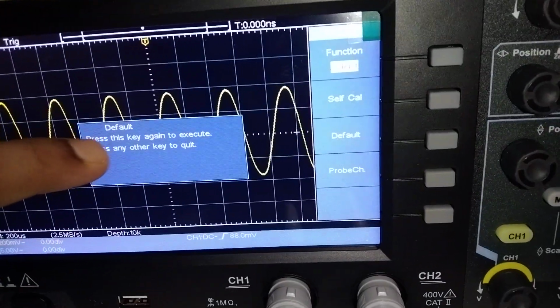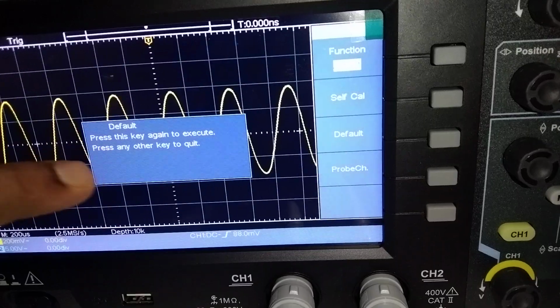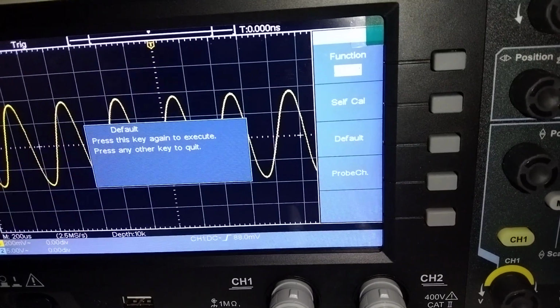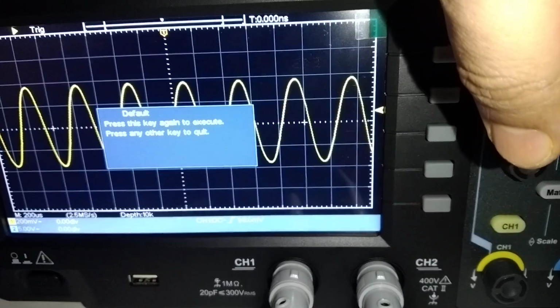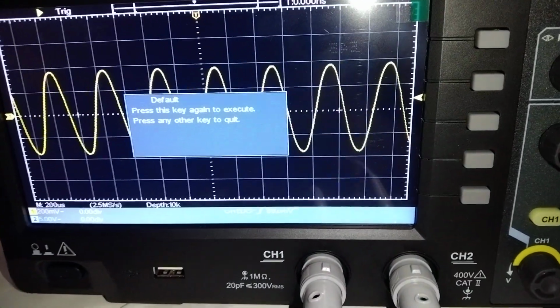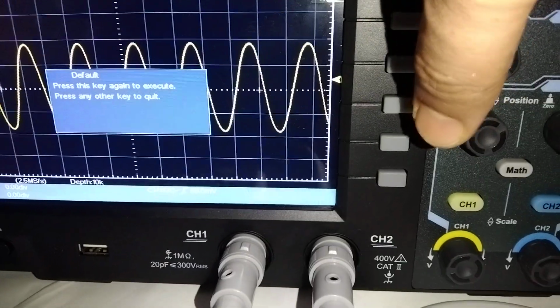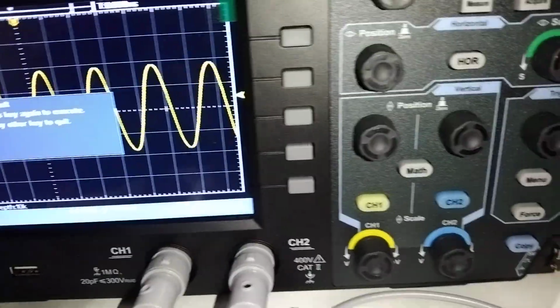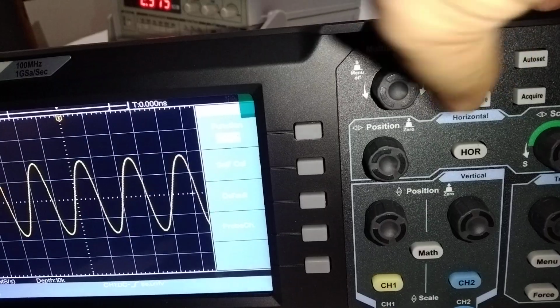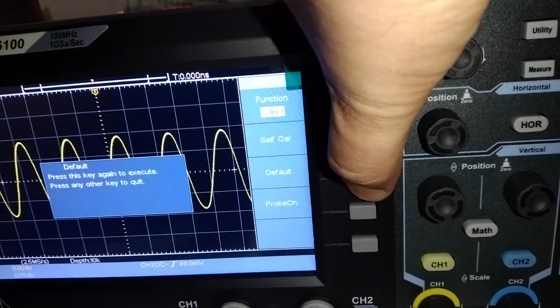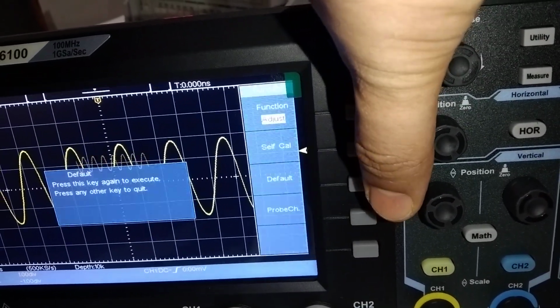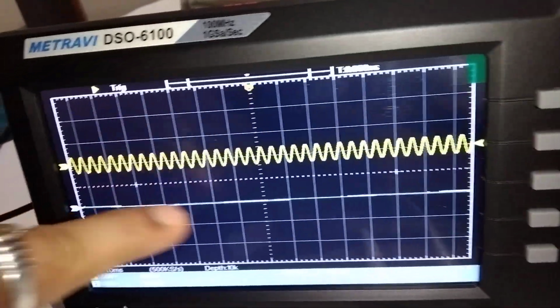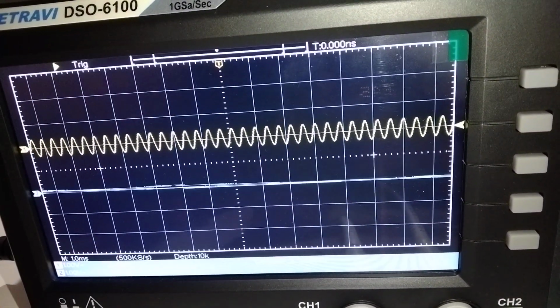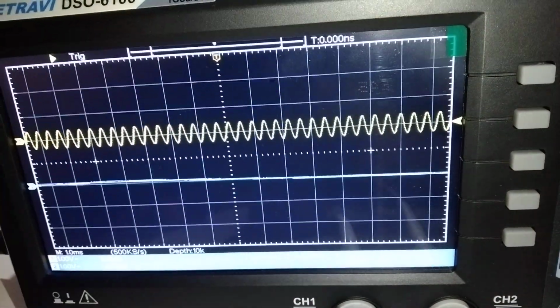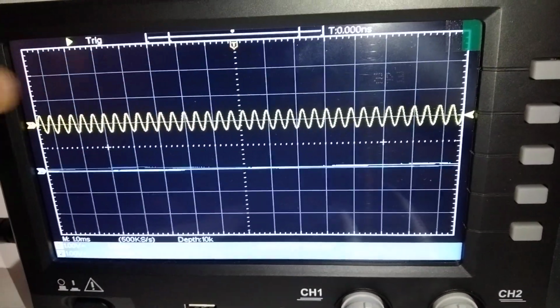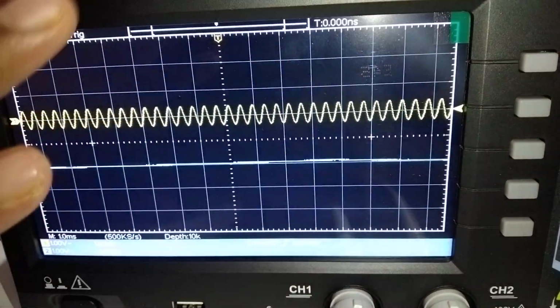Default: press this key again to execute, press any other key to quit. So the default attenuation coefficient set value of the probe. So you have to again press the default. So utility, default, then we'll execute. So here you can see that channel 2 has appeared. Initially there was no channel 2. I hope you understood. Initially only channel 1 was there. Now both the channels are introduced.